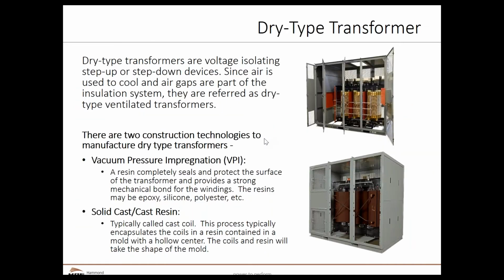With a dry type transformer, the transformer is, as we say, surrounded by air. And the heat that the transformer generates and needs to be cooled by is directly transferred to the air that circulates around it. In this case, you can see the core and coils. There are two main types of medium voltage transformers, what we call VPI and another one we call cast resin. Some people call it cast coil. The difference is how thick the resin coating is, or how thick that varnish that some people talk about is that covers the core and coils.